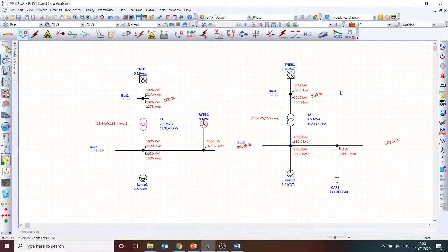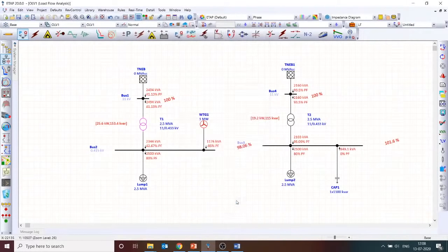Let's look at only the results here. Now the reactive power consumed by this load remains 1500 kVAR, but the capacitor is generating some reactive power. So the power factor at the grid is enhanced, right? Previously the power factor was 0.77. Now look at the power factor. It has increased to 0.935. So that means I am able to maintain the power factor better, and hence you need not pay any penalty. So this is how the industry works.